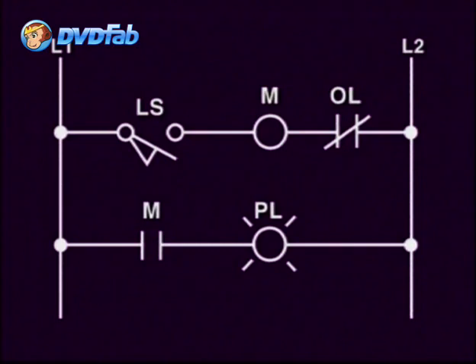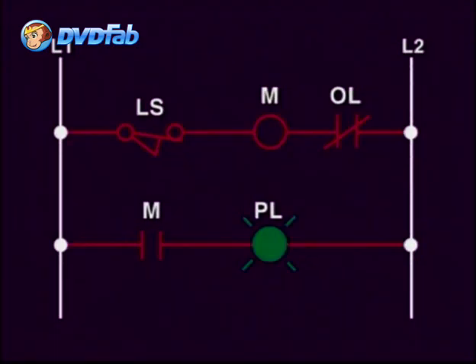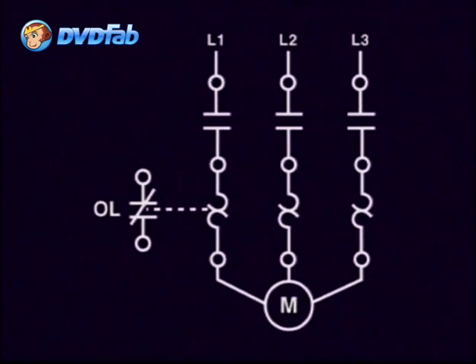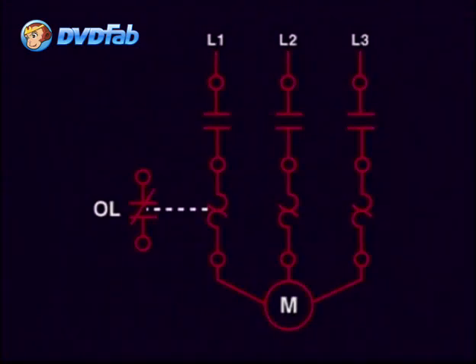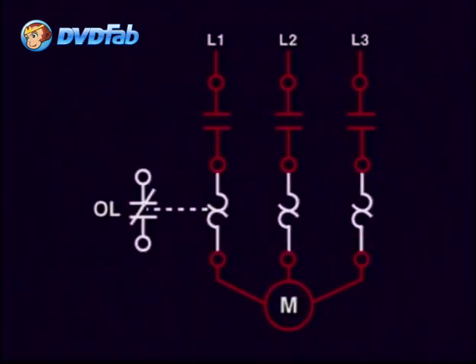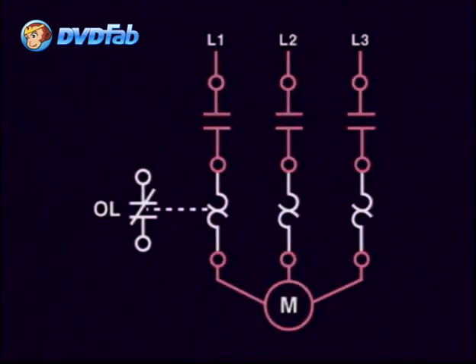In this ladder circuit, the motor starter will be on if the limit switch closes. Note that the normally open auxiliary contacts close and turn the pilot light on. The power contacts will close, providing power to the motor as soon as the starter coil is energized. If the motor pulls too much current, the overload relays will trip and open the normally closed overload contacts, which in turn disconnect the motor from the circuit. Later, we'll see this overload operation in more detail.